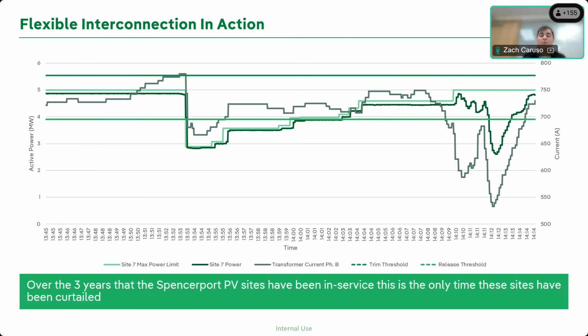And we can show it working. We can show it in action. This is an actual snapshot of time from Spencerport. You can see there are various shades of green, but the forest green line is the current on the bank, specifically the current on phase B. We can see it go over the trim threshold, which is this darker green line up here, and we can see the system rapidly take action. This lightish green line drops down from 5 megawatts, which is the full capacity of the site, to just under 3 megawatts of maximum output. The site's output, the darkest green line here, follows that max limit and drops down as well, and we see how that also drops the current.